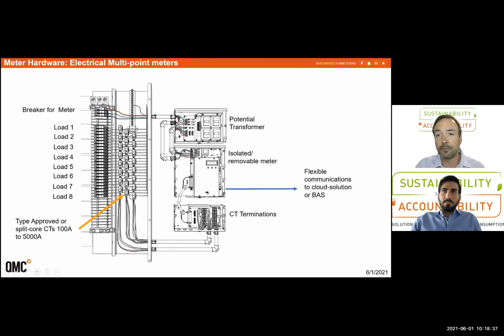You can do everything from 100 amp solid core CTs all the way up to 5,000 amp split core CTs. Quick note on split core CTs: those are only for information purposes. You cannot use those for billing applications within Canada. And last point here, we do want to get that data out of these meters in an open protocol, non-proprietary fashion. So whether you're sending that to a cloud-based system or you're communicating BACnet IP to the BAS, it's an important requirement of any meter to have that flexible communications out.